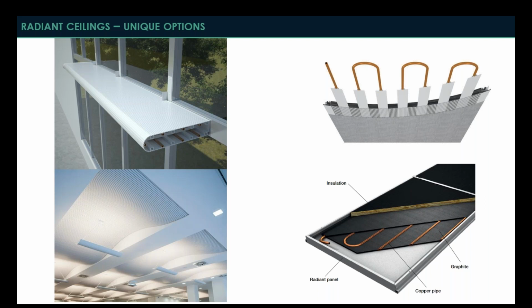In the bottom left, we see a radiant sail application, but this radiant sail is unique in that it actually has an acoustic fabric over it. And this acoustic fabric has been designed specifically to maintain the capacity of the radiant panel and the efficiency of its heat transfer. So anytime you put a piece of fabric or anything on top of a radiant panel, you're kind of adding an insulative layer and decreasing the performance. So some of the technology these days has been looking at how to create these fabrics that allow maximum heat transfer, but also provide a maximum acoustical benefit.